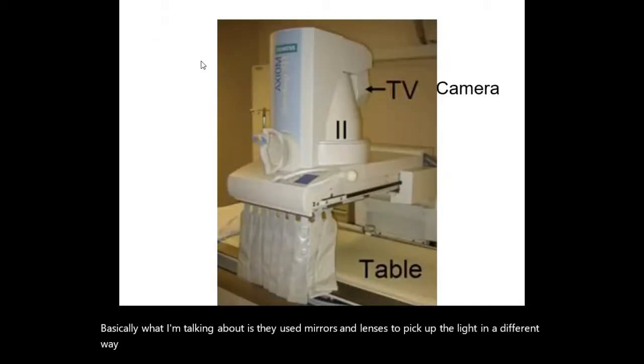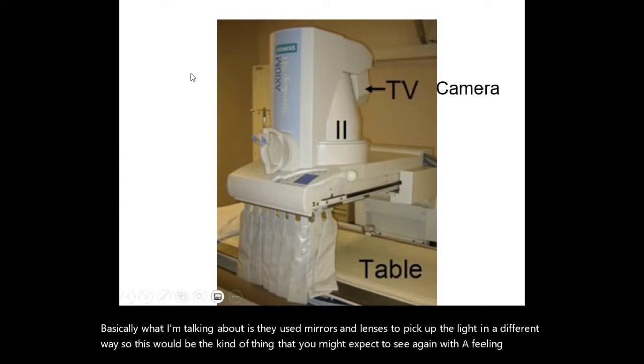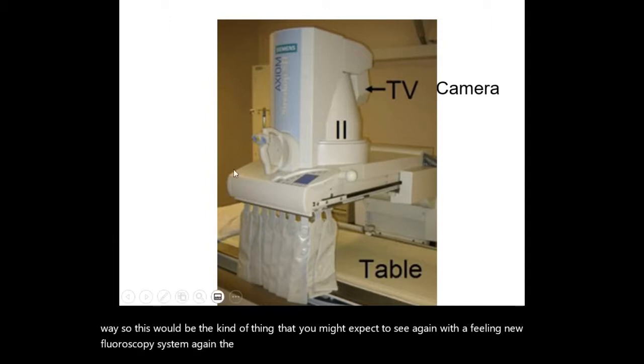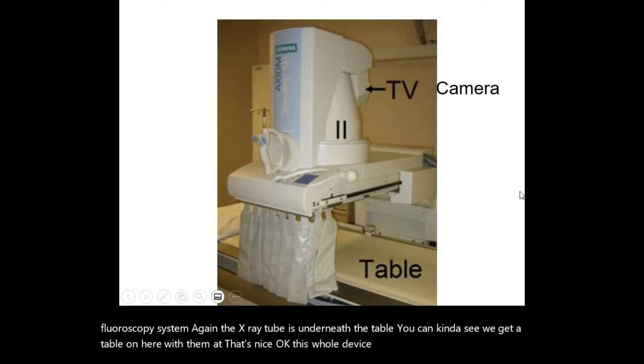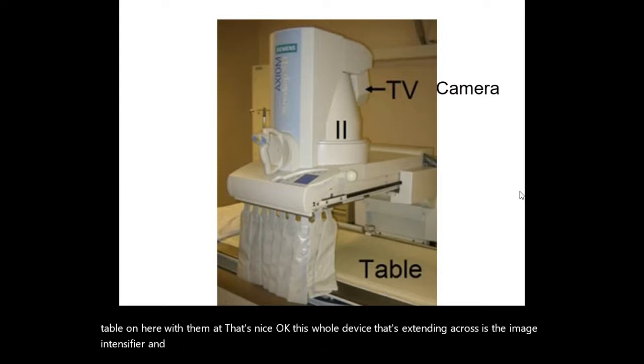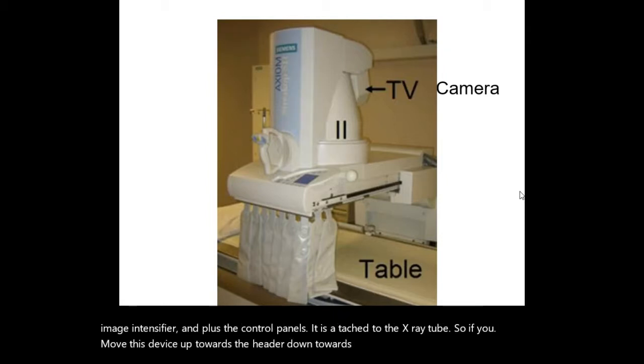So this would be the kind of thing that you might expect to see, again, with a fairly new fluoroscopy system. Again, the X-ray tube is underneath the table. You can kind of see we got a table on here with a mat. That's nice. Okay, this whole device that's extending across is the image intensifier, plus the control panels. It is attached to the X-ray tube. So if you move this device up towards the head or down towards the feet, the X-ray tube goes with it and remains centered. You don't ever have to worry about that.